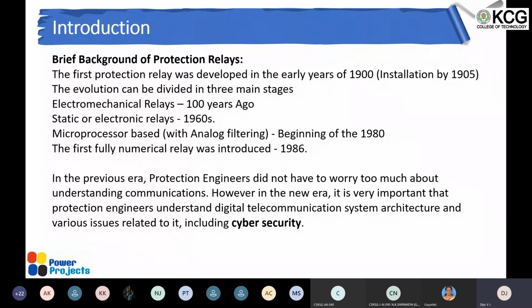But when the microprocessor-based relays came, and when the communication industry also developed, then people started utilizing more features from the relay, like communicating with the network and getting real-time information, and the voltage and current information would be sent to the other end to verify or to have a comparison, to ensure whether the feeder is faulted or not. Those things will be explained in detail in the upcoming slides.